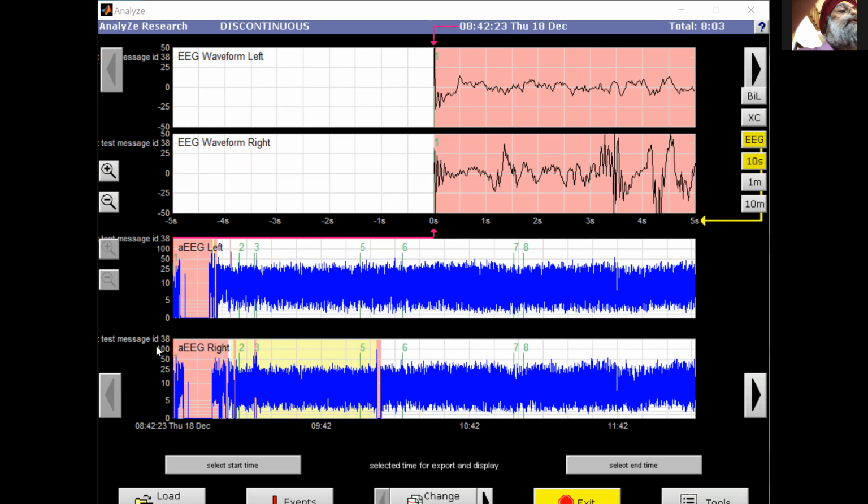I've noted with the hydrogels, if they are very close to each other, I get a lot of artifacts, like low voltage. Yes. And burst suppression spikes. Ah, the burst suppression spikes. I haven't seen that when they're so close together, but certainly I've seen the low voltage. So increase the distance and it reverts back to the normal background. Yeah, for sure. Okay, so we talked about sensor location. We talked a little bit about artifacts.